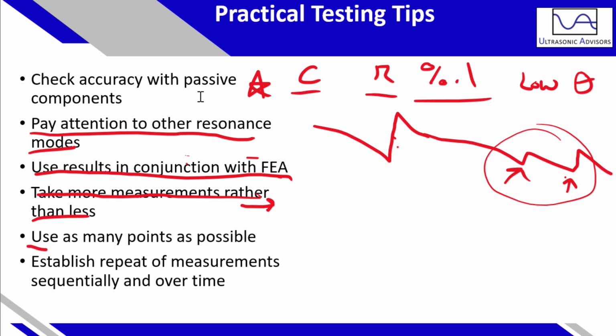Also, when you're doing your frequency sweep, use as many points as possible. Typically, I've seen either 1,000 or 1,600 points permissible in your frequency sweep. Use all of them. I think 1,601 is the limit on some of them I've seen. The one I was using doesn't have a limit because it's a custom setup. In addition to taking more measurements rather than less, record the raw data, the screenshot of the impedance, and also the summary parameters so you can quickly and easily compare.